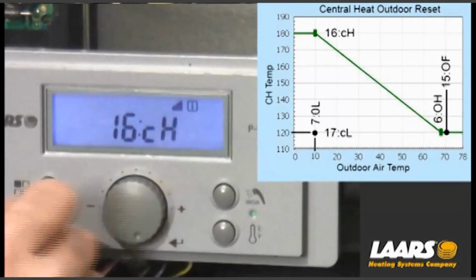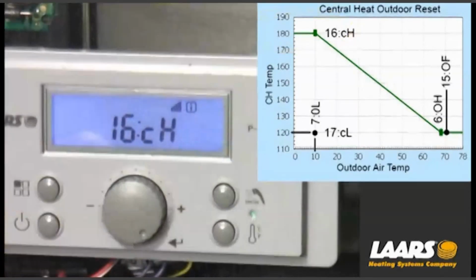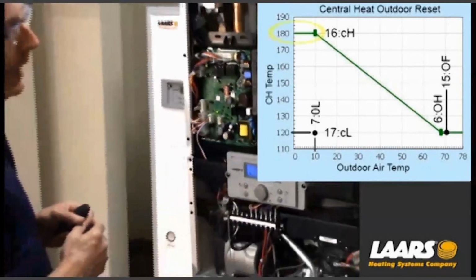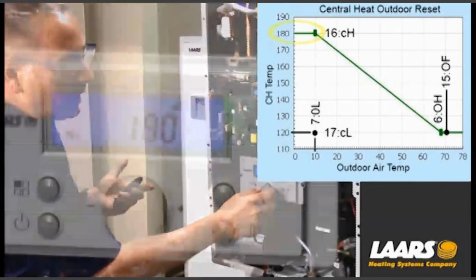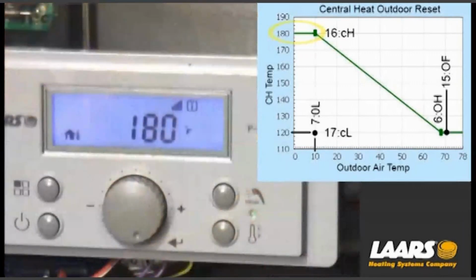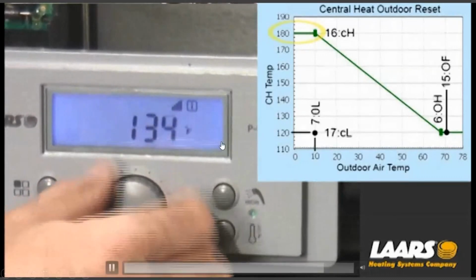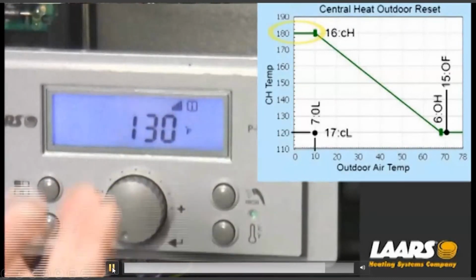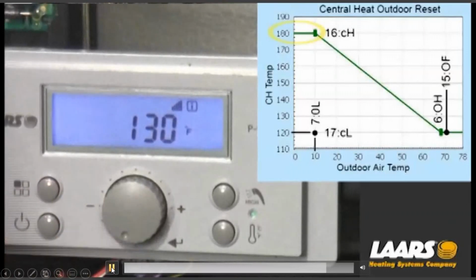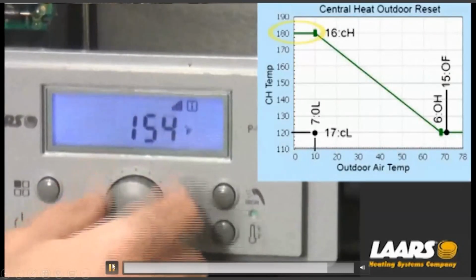Next, I want to turn the scroll button to 16CH. That is our central heat high. Okay, it should be defaulted, so 16CH. Press the select button. It should be defaulted for 180. However, if you've got in-floor radiant, and you don't want that temperature to ever go above, for example, 130, very simply turn that down. This is for the central heat only. Make that adjustment, press the select button, and it will store it.